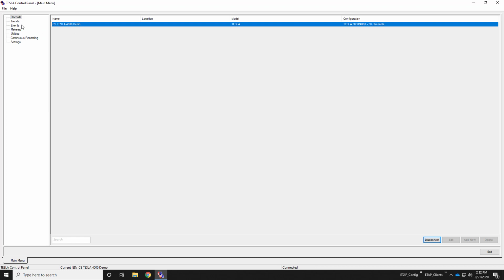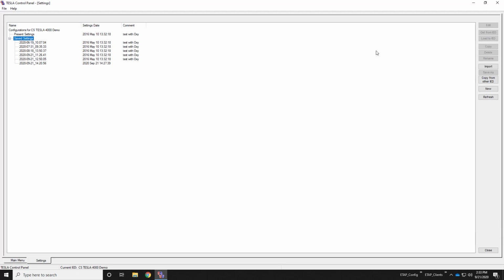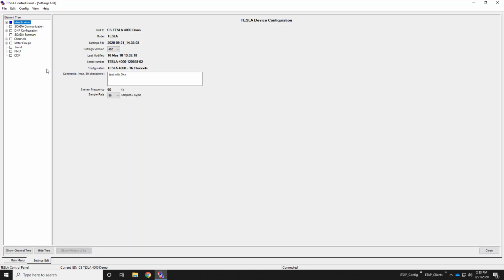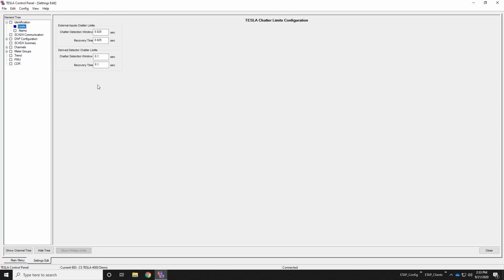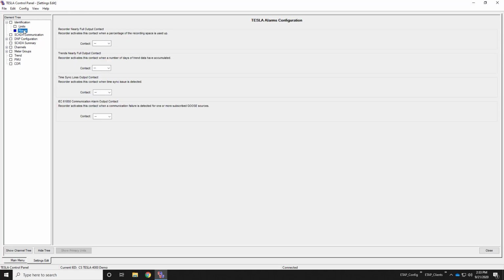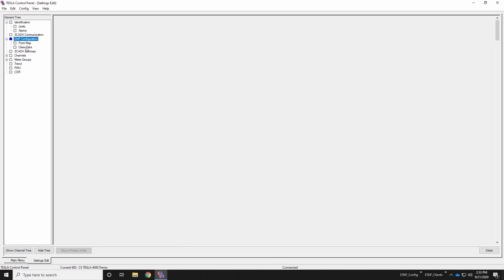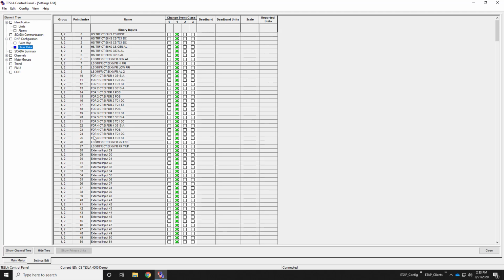Here I can go through and look at my settings first. I'm going to go to my present settings, get those settings from the IED, and I can download a setting here. Then I can double click those settings to see the actual details. Here I can set up my limits for my various parameters, set up alarm signals so I generate alarm signals based on various issues, as well as navigate to my DNP configuration, look at my class data, and look at my DNP mapping. If you have a SCADA, or if you use ETAP real-time to communicate to the device, you can set all that up here and then do the point mapping within the ETAP real-time environment.